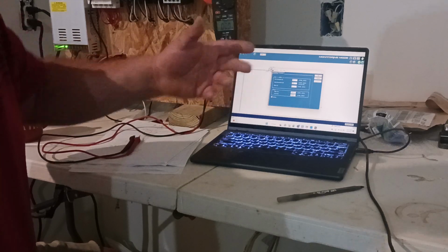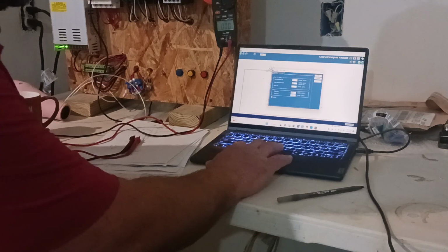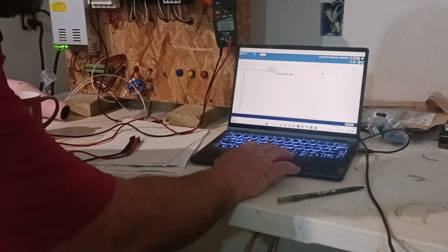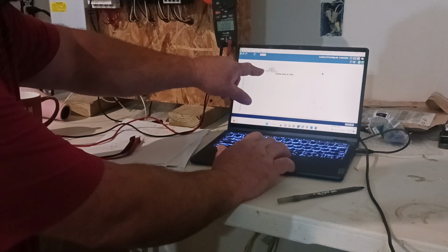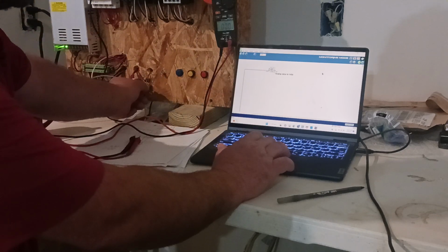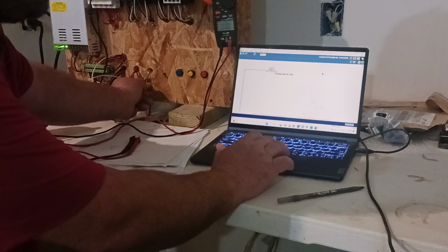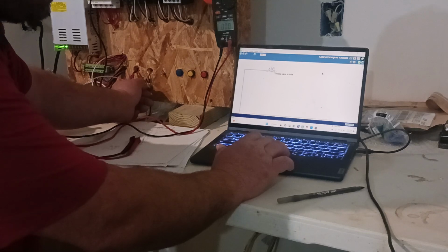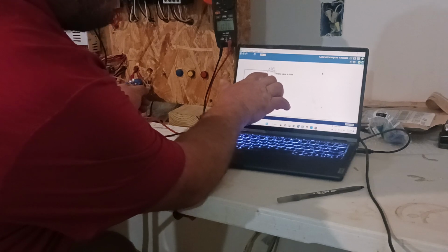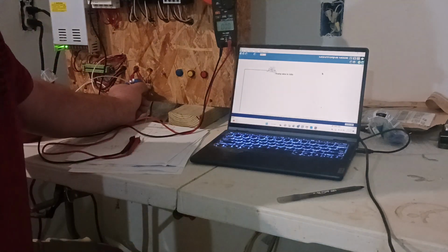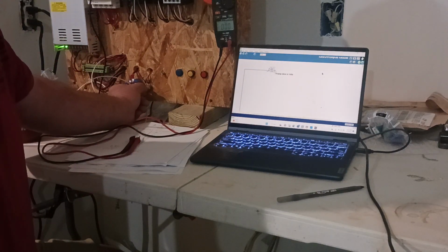So basically, my rate of change, how do I explain this? If I'm seeing 255, you can understand that if I go down to 1 volt, I'll basically have 25.5. Basically, every volt is 25.5, you could say.